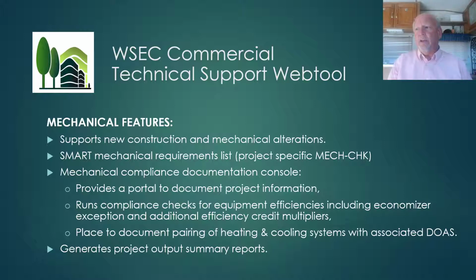We have our compliance documentation console, which I'll show you in a few minutes. It gives you the ability to document project information, run a compliance check for equipment efficiencies, including economizer exceptions and additional efficiency credit multipliers, and then finally a place to document pairing of heating and cooling systems with the associated DOAS system. What our tool does do is a good job of verifying compliance with equipment efficiencies, additional efficiency options, economizer exceptions, and ventilation. It does not cover all of the control system requirements. That's through the SMART checklist. And then finally, the web tool generates an output summary report that you can use to submit to the jurisdiction to document compliance.